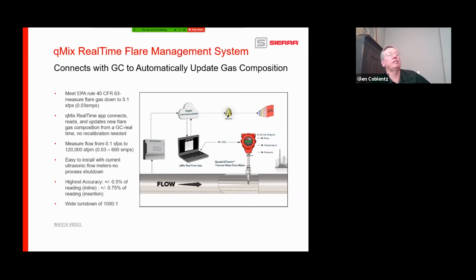What some of our customers are realizing is, hey, this can handle everything. I don't need the multipath ultrasonic. This will handle it all. Right now, we're just really focusing on this, letting the multipath ultrasonic handle everything else. You've got an easy to install meter. Typically you're going to have either a 300 or 600 pound flange. I understand the flare gas is atmospheric, but there are piping codes on refineries where any flange has to be a certain rating, so you work up whatever you need here, and they're all hot tapped. They'll be put into the pipe, and you get huge turndown.